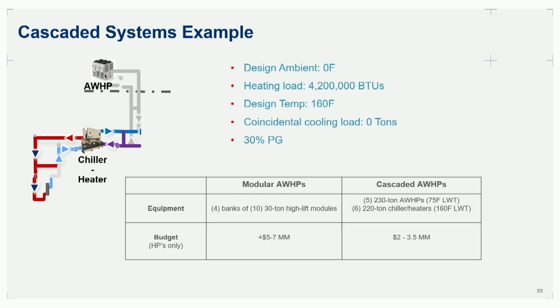Now, if you were to do this, what I would call the blunt force or brute force method, where you want to do this with a single machine or a single bank of machines, this is essentially specialty equipment to take 0 degree air and make 160 degree water out of it. It exists, Trane has products that do this, but at this size, in this case, it looks like you're going to need 40 modules in order to hit that. Modular equipment is not cheap, and it takes up a lot of space, especially on the air side. And so if you were to add up those 40 modules and what it would actually cost to hit that capacity, it'd be around $6 million for the heat pumps themselves.